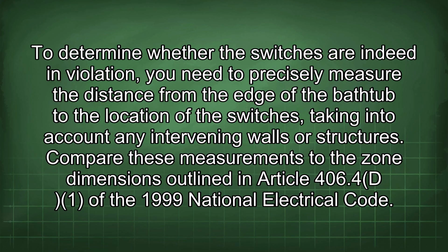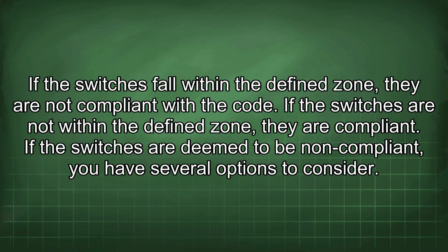Compare these measurements to the zone dimensions outlined in Article 406.4d of the 1999 National Electrical Code. If the switches fall within the defined zone, they are not compliant with the code. If the switches are not within the defined zone, they are compliant.